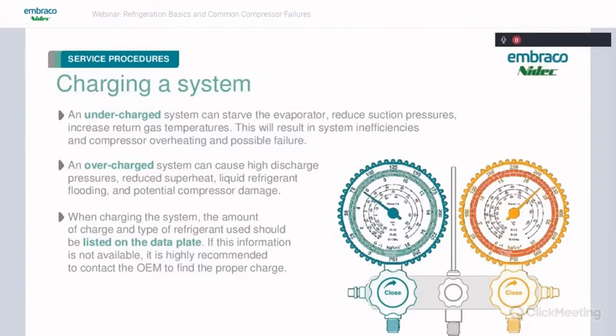So an overcharged system is going to cause high discharge pressures, reduced superheat, which means liquid refrigerant flooding and potential compressor damage, because we don't want any liquid refrigerant to enter that compressor. When we're charging the system, the amount of charge and type of the refrigerant should be listed on the data plate of the unit. If this is not available, it's recommended to contact the OEM to find the proper charge, because we always want to weigh in that charge after service as possible. It just removes a lot of possibilities for problems when you weigh it in.